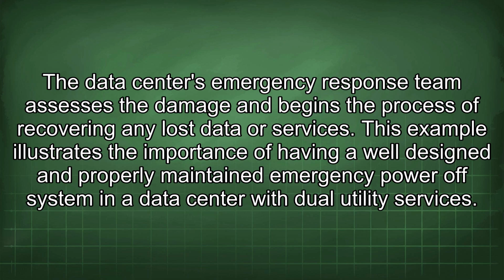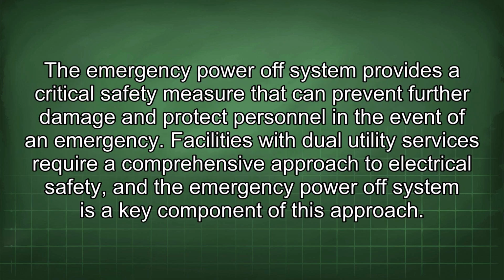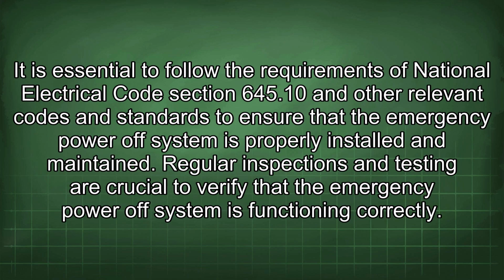This example illustrates the importance of having a well-designed and properly maintained emergency power-off system in a data center with dual utility services. The emergency power-off system provides a critical safety measure that can prevent further damage and protect personnel in the event of an emergency. Facilities with dual utility services require a comprehensive approach to electrical safety, and the emergency power-off system is a key component of this approach. It is essential to follow the requirements of National Electrical Code Section 645.10 and other relevant codes and standards to ensure that the emergency power-off system is properly installed and maintained.